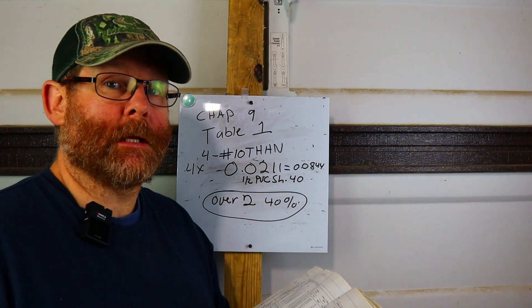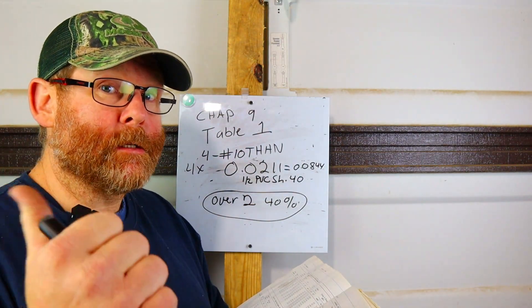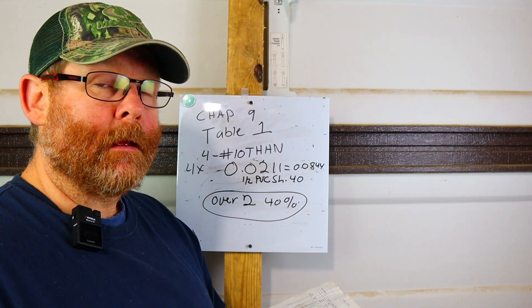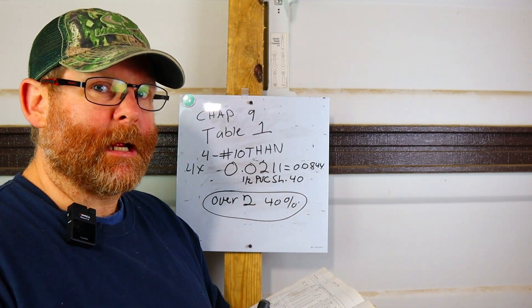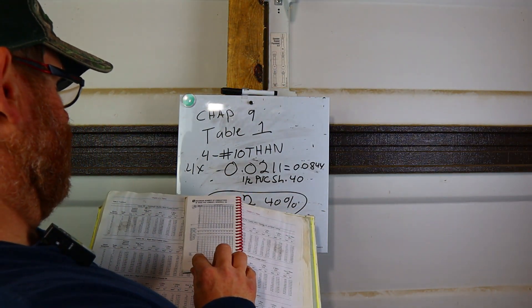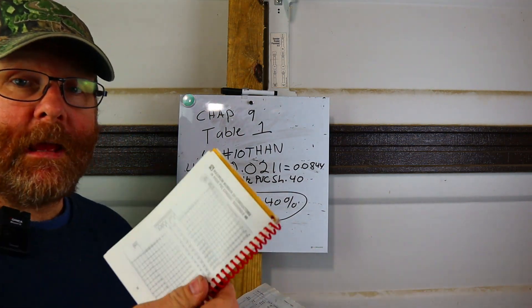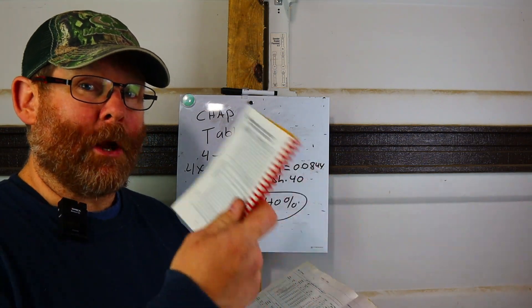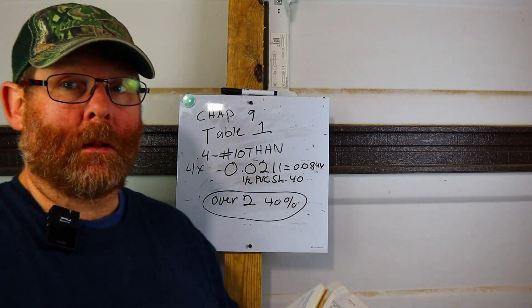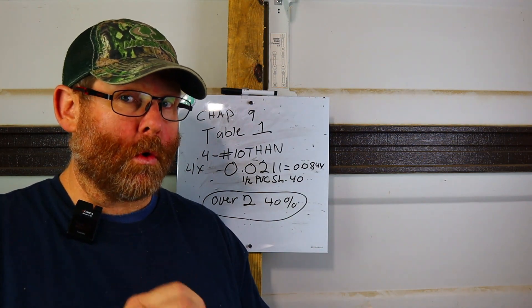Let's verify against the Ugly's book. Look up THHN number ten — it says you can get five in a half-inch PVC schedule 40. That confirms the math is right. It already takes everything into account. Now let's do the number sixes so you can see the full process.